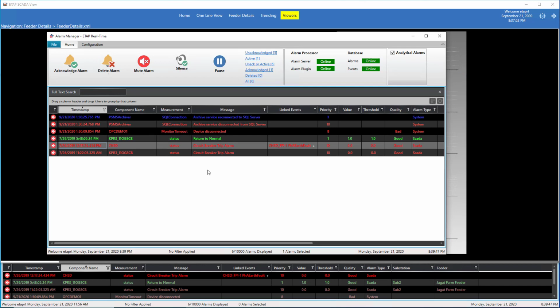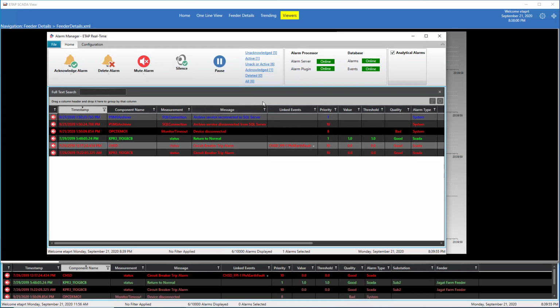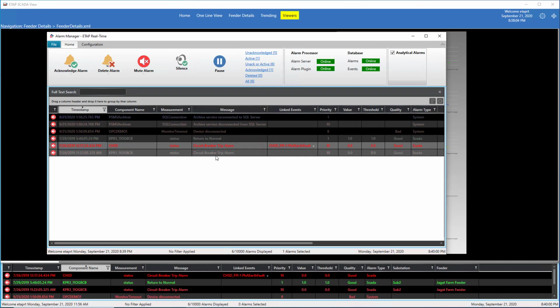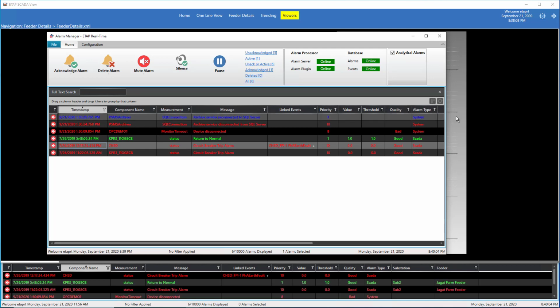We also have capabilities for unmanned substations where there is no local operator in the substation. So we have features for automatic acknowledgement of alarms, although the alarm system is also sending this information to the remote stations and SCADA systems.